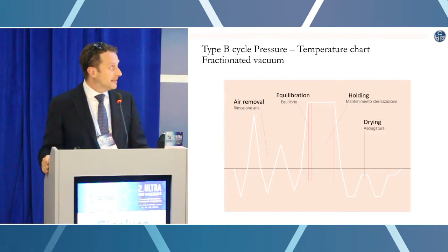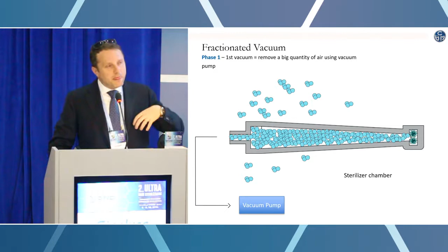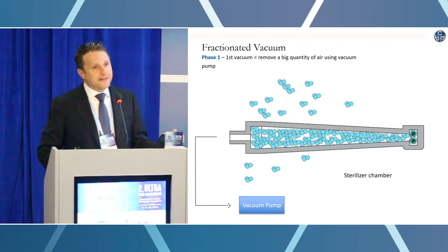So almost all steam sterilizers, or let's say the state-of-the-art steam sterilizers, use the fractionated vacuum air removal system. What does it mean? Practically, it's a sort of pumping inside of the load. Here are visualized the dental handpieces where we have the pathogenic material at the end, ready to be transmitted into your mouth, and a lot of air trapped in the turbine. We first have to remove the air from the inside. By alternating vacuum and steam injection, this air will be continuously sucked and pumped out from the load until almost all of the air has been removed from the turbine, so we can sterilize.